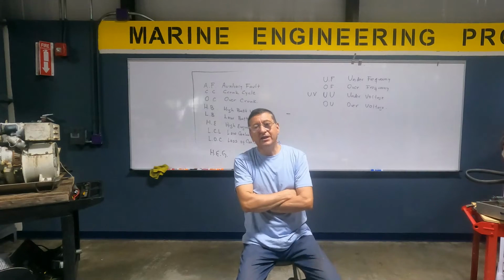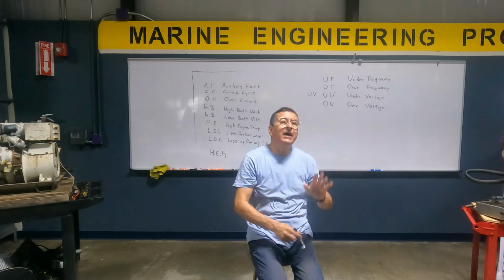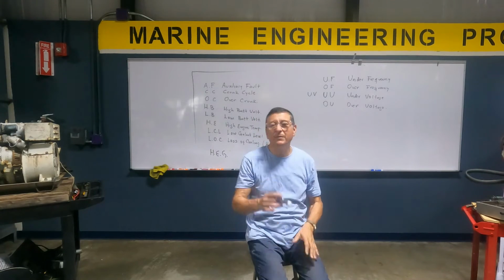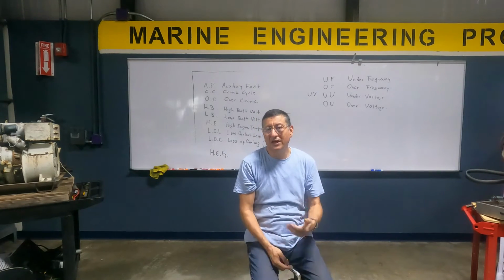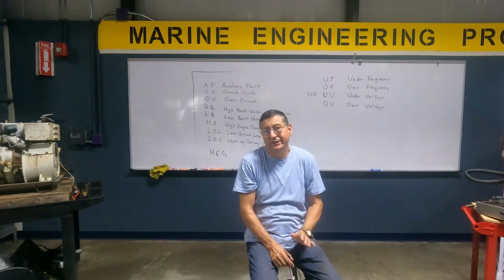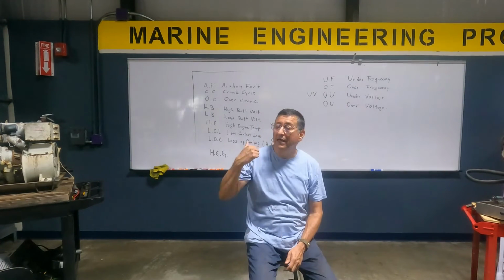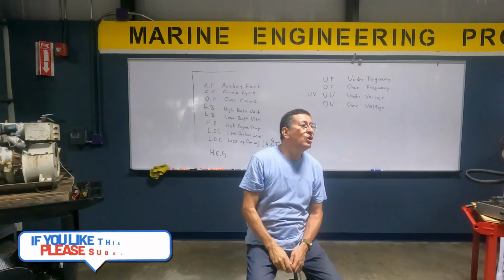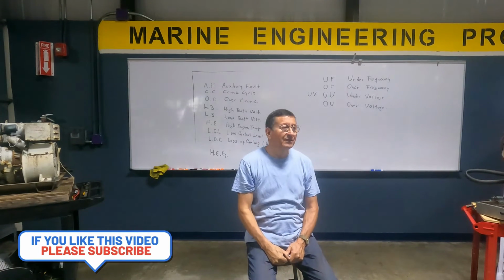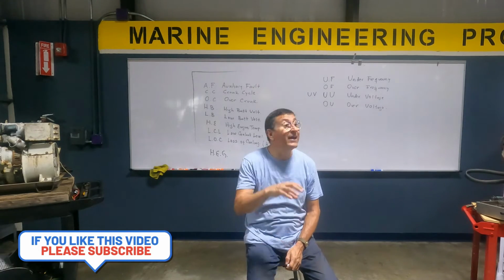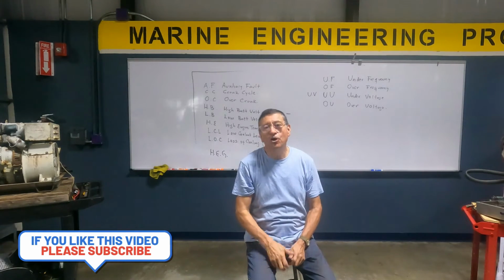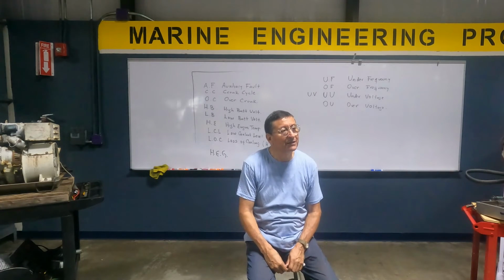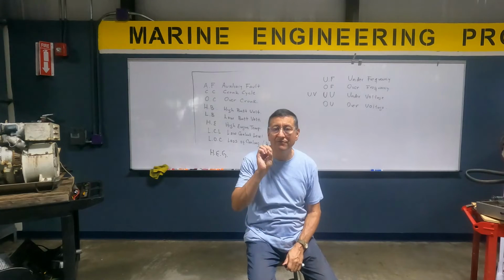The engine is running and stops suddenly and displays a code: low frequency, high frequency, low voltage, high voltage. Normally it's one of those. In some generators, when they try to start, they crank but do not start, and they show a code low excitation. The excitation in the exciter is low and does not produce enough magnetism to create power.